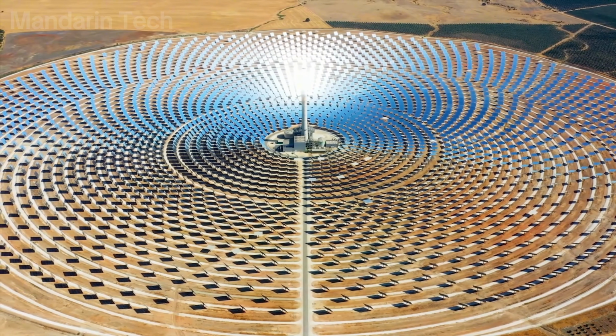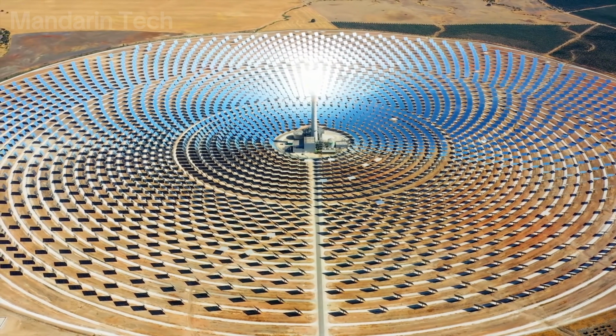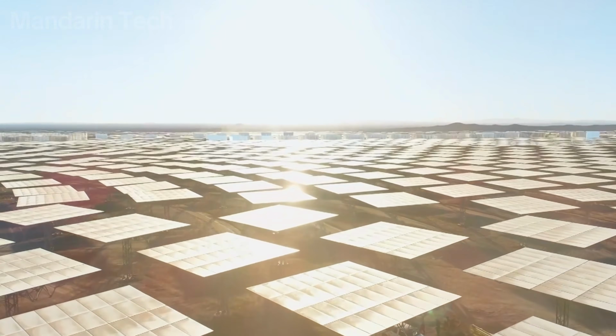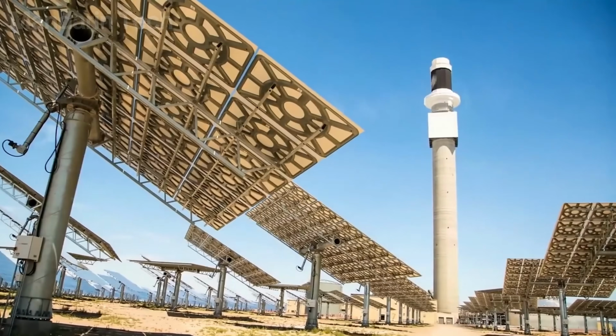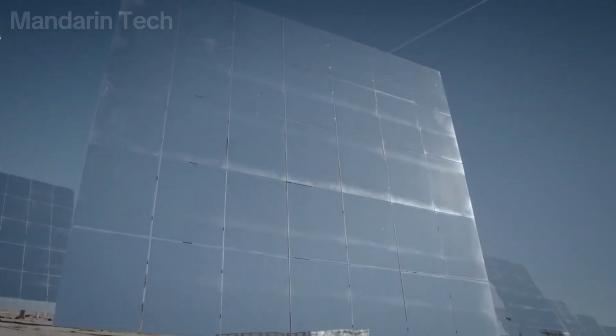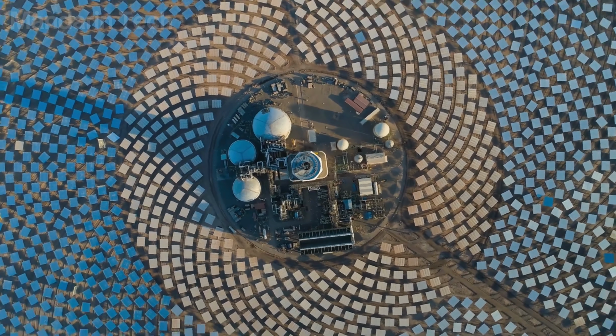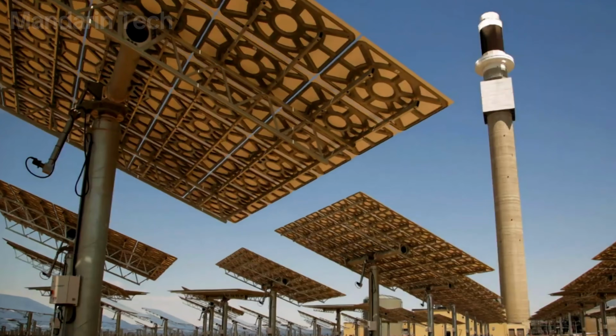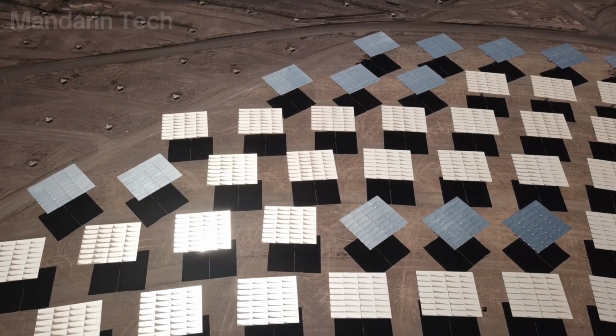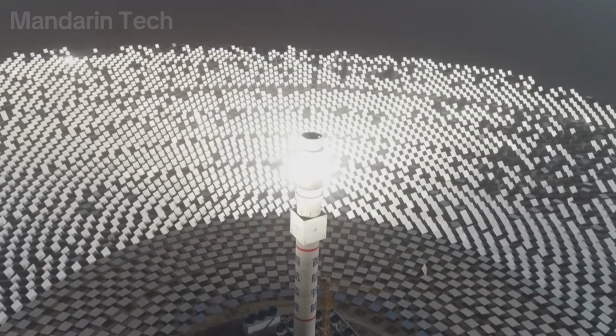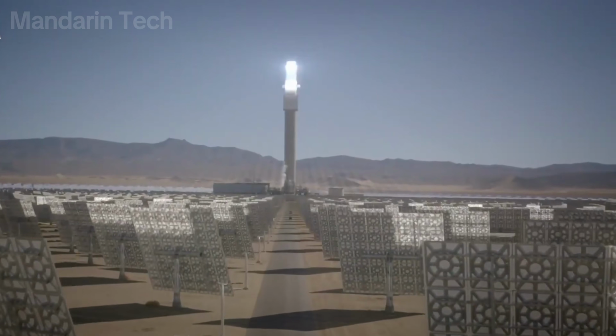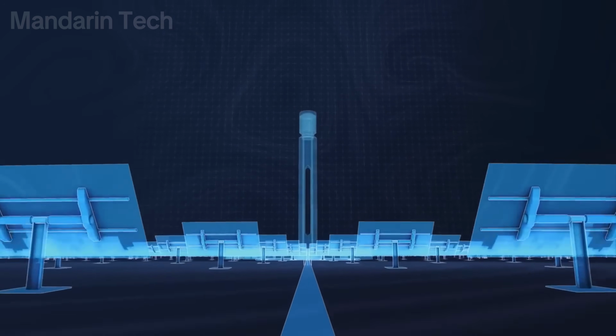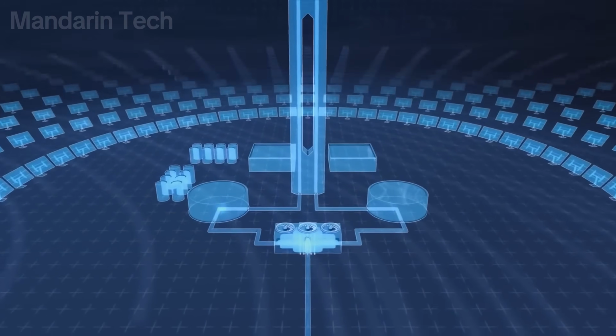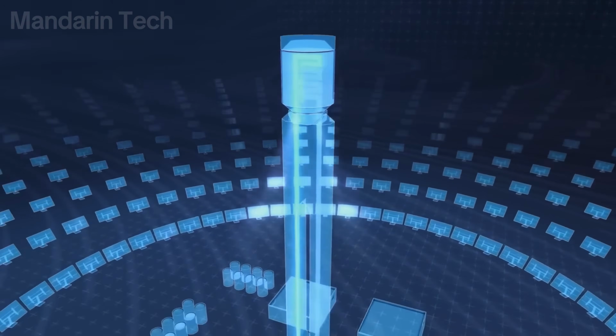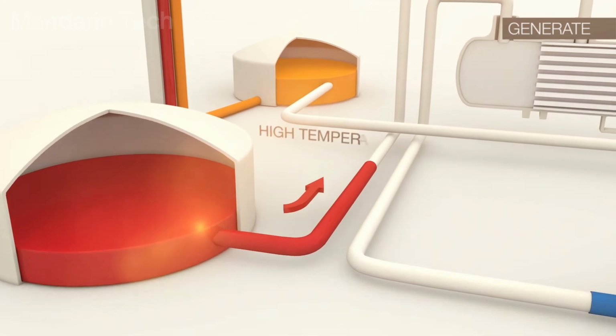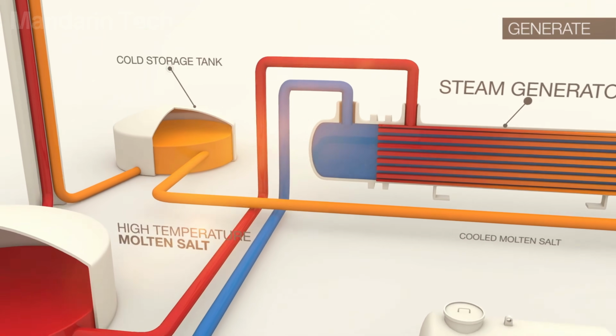Once all components were completed, Cerro Dominador entered the commissioning phase. More than 10,600 heliostats were divided into separate zones and sequentially reflected sunlight toward calibration targets on the tower. Cameras recorded the reflected spots, while software measured deviations and sent adjustment commands to the motors of each mirror. Once the required accuracy was achieved, part of the heliostat field was directed toward the receiver, while thermal cameras monitored the energy distribution. At the same time, molten salt was pumped through the system at a low flow rate, and the valves were opened sequentially to control temperature and pressure.